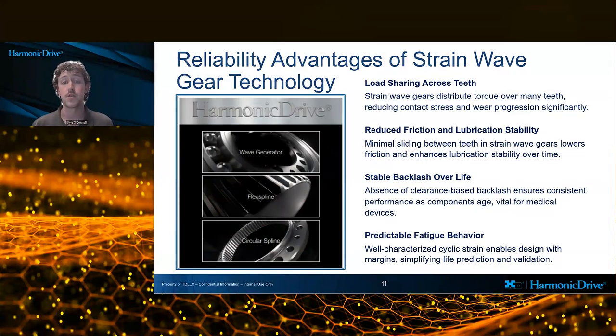Now we're going to get into why strain wave gears reduce that likelihood. They offer a few intrinsic reliability advantages that make them well-suited to medical applications. One of the most important is load sharing across multiple teeth at once. Unlike conventional gears where the load is concentrated on a small number of teeth, strain wave gears distribute that torque over multiple teeth in a large contact area. They spread out the contact stress and it slows the wear progression.